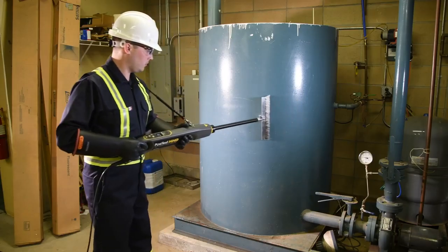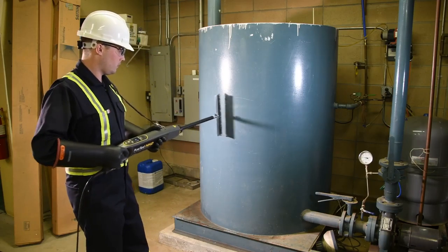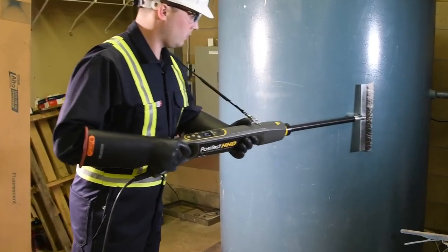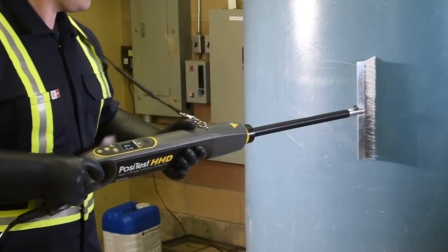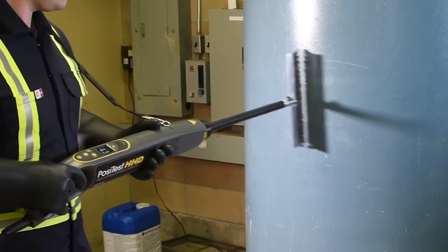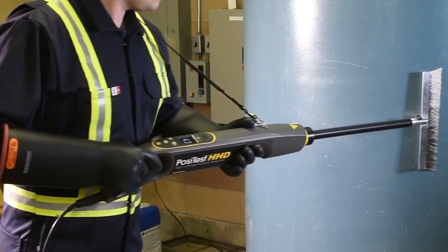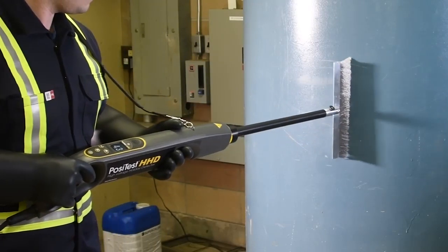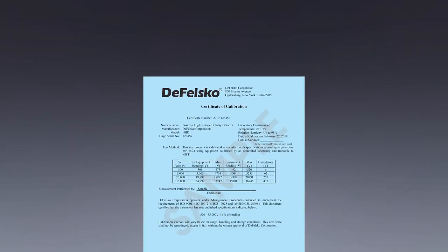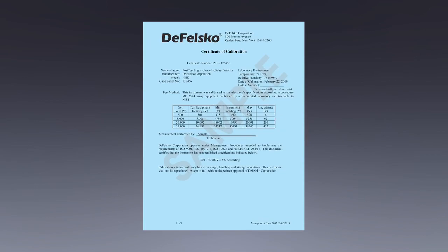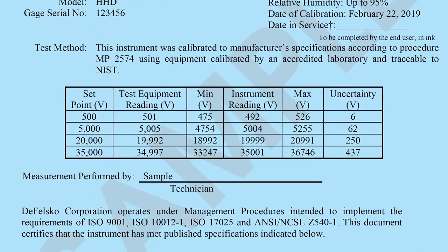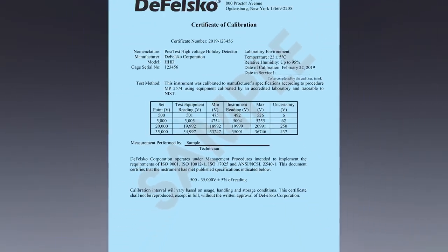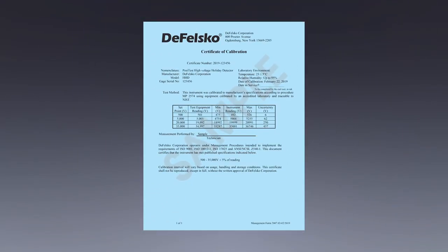It has a built-in calibrated crest meter that constantly measures the voltage at the electrode while testing. The voltage on the screen is the actual voltage at the electrode, not the set voltage, like on many competitive models. Included at no cost is a long-form certificate of calibration documenting actual Positest HHD readings on traceable laboratory equipment, certifying that the Positest HHD is testing at the correct voltage.